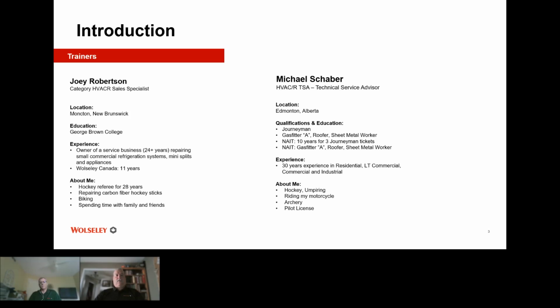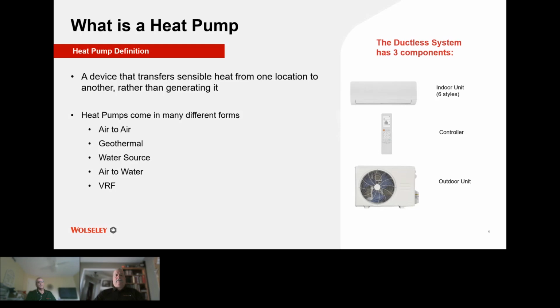So question is, what is a heat pump? A heat pump is a device that transfers sensible heat from one location to another rather than generating it. So it just moves heat from one part to another, basically. There's different forms of heat pumps. There's air to air. That's what we're going to be concentrating on most today because that's the most popular. There's the geothermal, which is the most efficient, but unfortunately it's also the most expensive to install. You have a water source heat pump, an air to water, and a VRF. And over to the right, we have a ductless system, the components. Basically you have your indoor units, your controller, and your outdoor units. And your indoor unit will come in many different forms depending on what you choose for the outdoor.